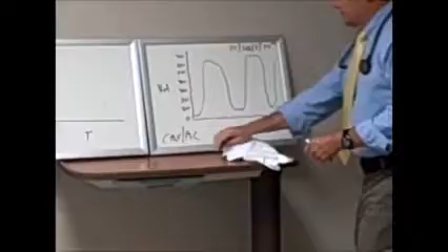So the only work of breathing he's doing is what? It's the sensitivity when he triggers the demand valve. That's why it's called assist control or controlled mandatory ventilation. The only work of breathing he's doing is the amount of negative pressure he has to generate to open the demand valve. Open that valve. Okay? And every breath will look exactly the same. Okay? So let's do it. See, machine breath, 600. Same thing.